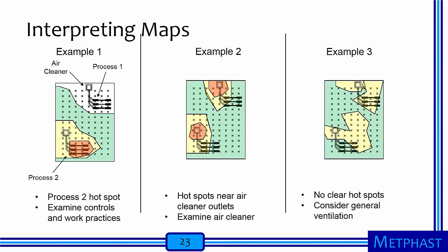Such maps can yield extremely useful information. In the example on the left, a red hotspot is observed at process 2, and the best course of action is to examine the controls and workplace practices in this area — workers at the two processes would be grouped into different SEGs. In the middle example, hotspots are observed at the exhaust of the air cleaners, indicating that attention should be paid to evaluate the air cleaner. In the third example at right, there are no clear hotspots, and general exhaust ventilation should be considered to lower concentrations throughout the facility.